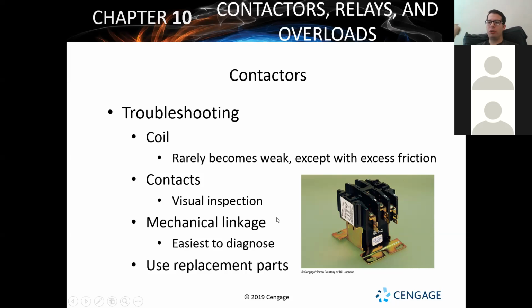Click, burn. As soon as that happens, this little guy is going down. If it has dust, debris, bugs, mice, fur or gunk caught up in there, that builds resistance and means we don't have a clean contact. When that armature doesn't come down perfectly flat, if it comes down at a bit of an angle before it flattens out and makes that perfect connection, that's when you're going to see that spark like you would in your wall switch. That spark leads to major problems, and that's what causes those burn marks.